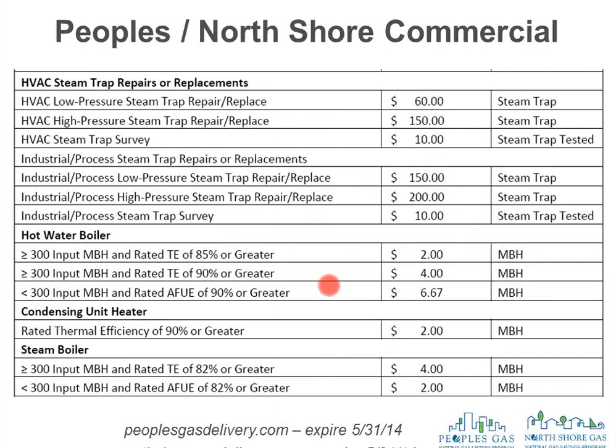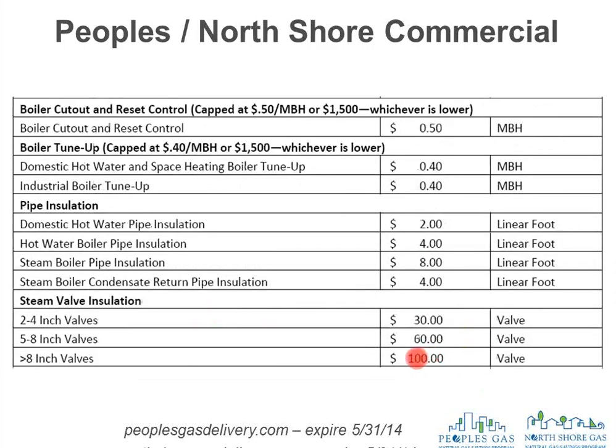And by the way, generally multifamily, condo buildings and apartments count as commercial buildings for most of these rebate programs, generally speaking. There are rebates for hot water boilers. If you put in a condensing boiler, 90% efficient and better, over 300 MBH, it's $4 per MBH that ends up being your rebate. If it's smaller than that, it's $6.67 per MBH. Not sure who was figuring that one out, but they didn't like rounding. Rebates for condensing unit heaters, rebates for steam boilers, rebates for outside air reset controls. Once again, there's a maximum on that, $1,500, 50 cents per MBH. There's rebates for tune-ups, also capped at $1,500, 40 cents per MBH.